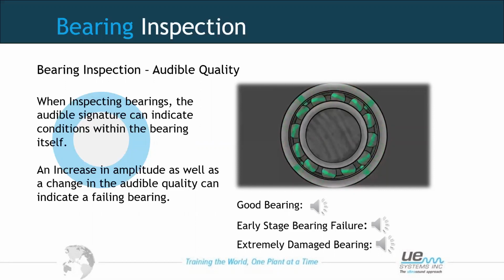What we're going to pick up with the ultrasound. There are no limitations in terms of the type of bearing. Not only ball bearings, other types of bearings can be checked. So again, any type of rotating asset or rotating bearing will generate friction, so we will be able to pick up the ultrasound emission coming from that bearing. So it doesn't matter on the type.